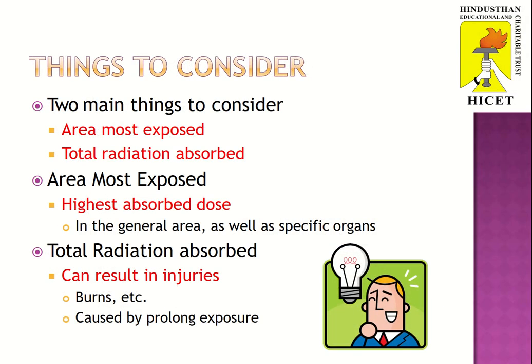There are two main things to consider during fluoroscopy. The first is the area most exposed, meaning the highest absorbed dose in the general area as well as specific organs. The second is the total radiation absorbed, which can result in injuries and burns caused by prolonged exposure.